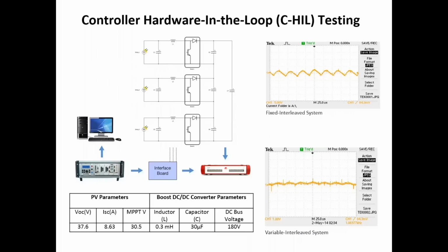And where it actually helped us a lot is that when we were commissioning these kind of big utility converters, we would see a lot of things on the grid that we could not explain. And so instead of playing around on the real system, because things might blow up, we came back to our simulators, and we would recreate the grid scenarios that we would have seen, and then try to develop controllers that would take care of or let us operate in those conditions.